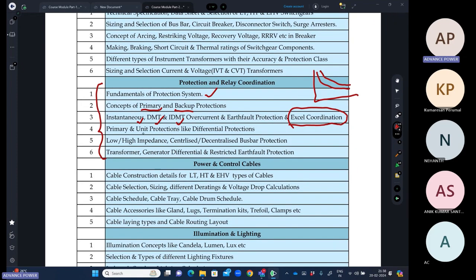We'll discuss the primary and unit protections. So unit protection like differential. We'll discuss the transformer differential, generator differential, motor differential here. We'll discuss the restricted earth fault protection also. So why even having a differential protection, we are also using the restricted earth fault protection.